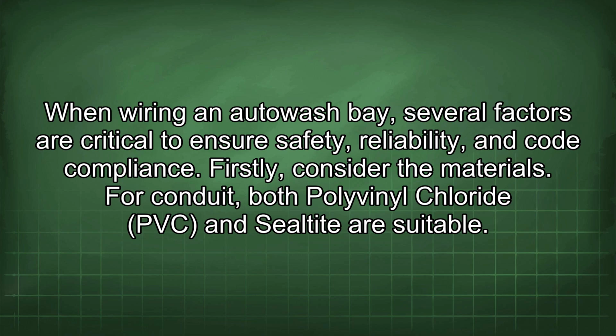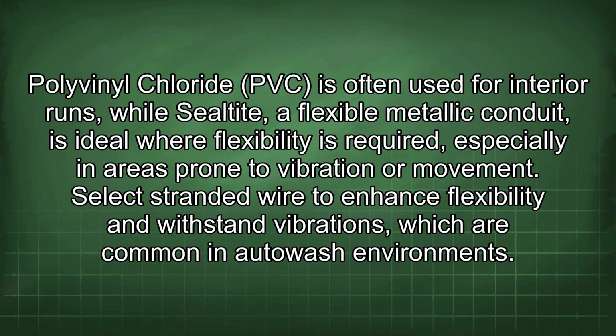Firstly, consider the materials. For conduit, both PVC and Sealtite are suitable. PVC is often used for interior runs, while Sealtite, a flexible metallic conduit, is ideal where flexibility is required, especially in areas prone to vibration or movement.